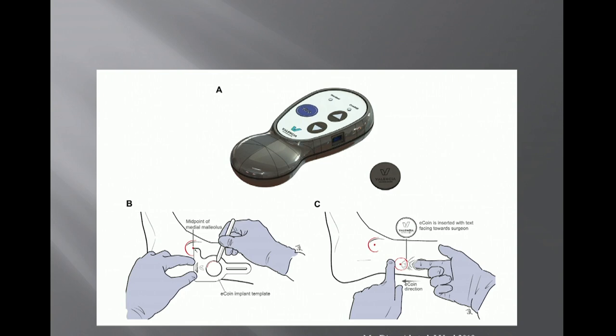A positioning device helps mark where the implant will sit, then a small incision about a half to one centimeter cephalad is made and the device is tunneled into a pocket. It's activated four weeks after implantation, automatically programmed to stimulate every two days for 30-minute sessions, then every 15 days after 12 weeks. Because it's intermittent stimulation, the batteries should last a long time without frequent changes.